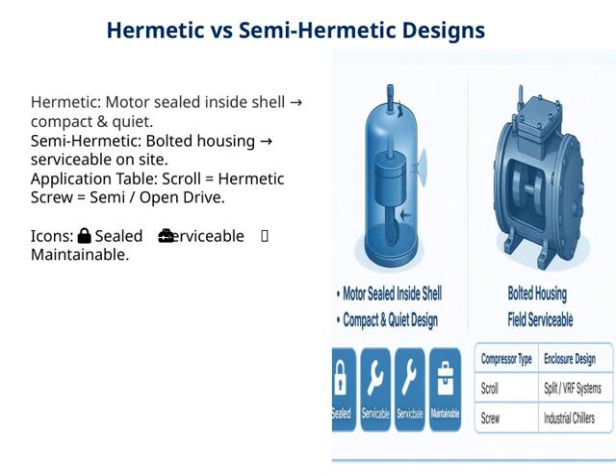Now, if we look at the application table, you'll notice that scroll compressors are typically hermetic, indicated by the locked icon, emphasizing their sealed nature. Screw compressors tend to be semi-hermetic or open drive, which is shown by the nut and bolt icon, highlighting their serviceability. The icons here are helpful. The locked symbol reminds us of the sealed, maintenance-free aspect of hermetic designs, while nut and bolt and toolbox point to the serviceable and maintainable qualities of semi-hermetic units. Understanding these differences is crucial when selecting the right compressor for an application, especially considering factors like noise, accessibility, and maintenance needs. This choice directly ties into the overall theme of optimizing system efficiency and reliability.